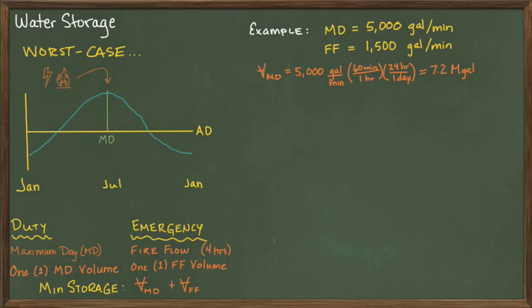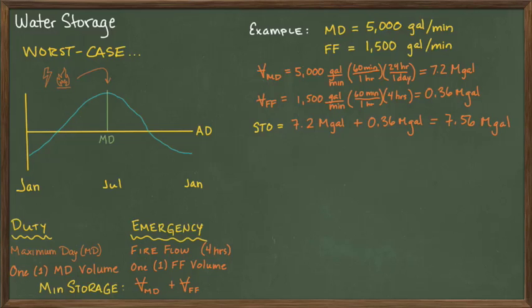Next, we do the calculation for the fire flow volume, which is the same as the max day demand. But the difference is that instead of 24 hours, you multiply by only 4 hours. And this yields a storage of 0.36 million gallons. So for this exercise, the storage is 7.2 million gallons plus 0.36 million gallons to get a total of 7.56 million gallons.